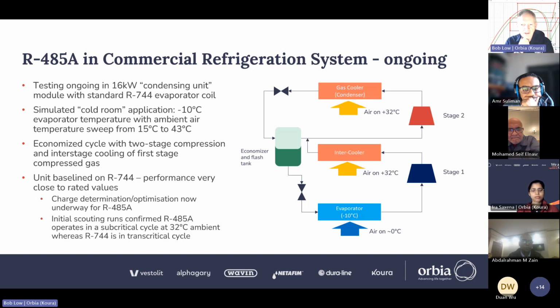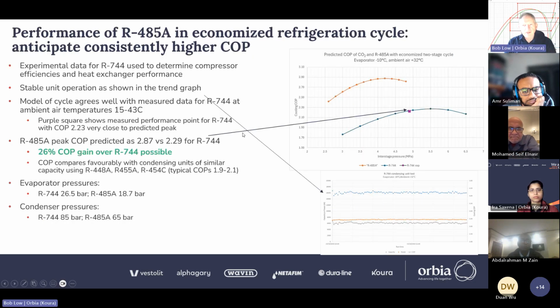But what we do know is, similar to the heat pump water heater I talked about earlier, at 32C ambient, the blend sits as a condensing subcritical refrigerant, not as a transcritical refrigerant. So what do we expect to see? Well, we haven't got the measurements yet, but coming soon. We'll present them in Birmingham, in Manchester in August. If we take the data we do have and build a cycle model and take into account the heat exchange areas and so on, what we can predict is that we should be able to get an optimum COP for the blend that's 25% better than CO2.